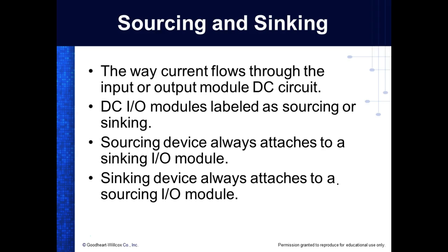By the way, they very seldom call them sinking and sourcing sensors. And we're not going to explain this. I'm going to just give it to you. Take it for granted. An NPN sensor is a sinking sensor. A PNP sensor is a sourcing sensor. If you take solid state devices, we talk a little bit about it in advanced PLCs.